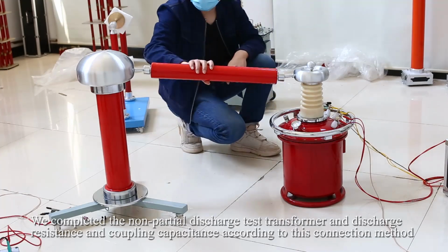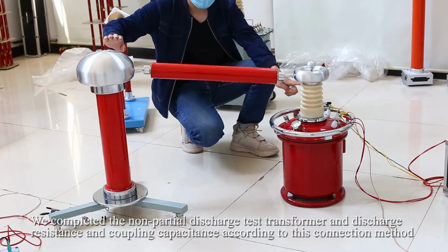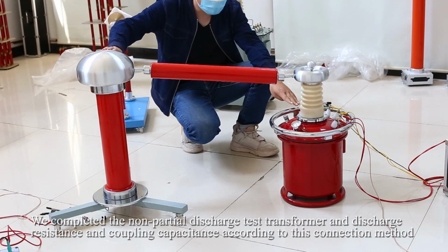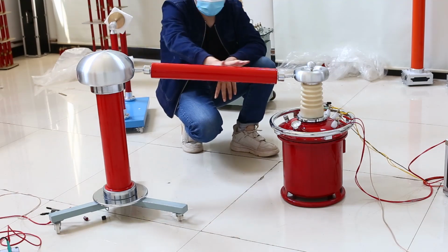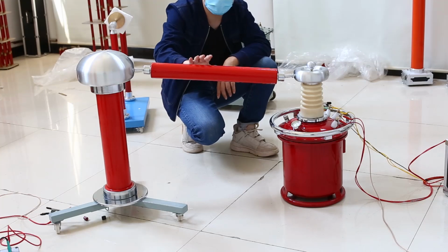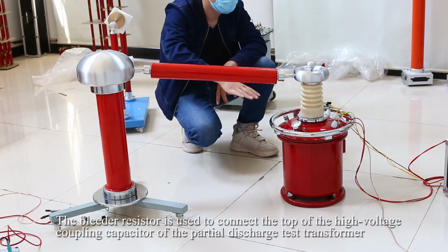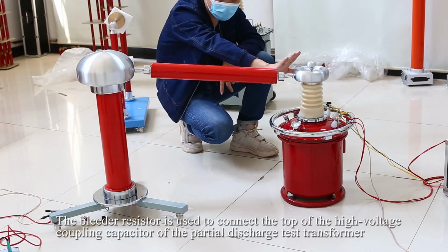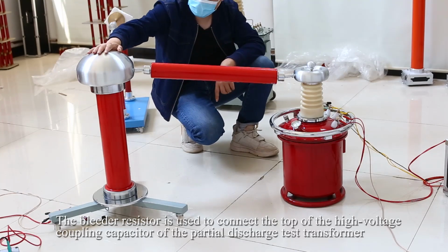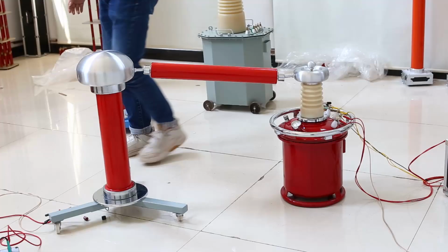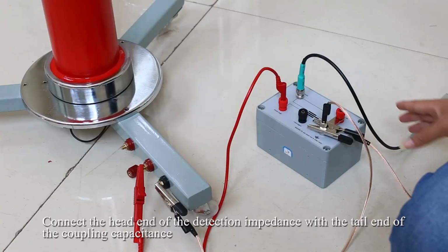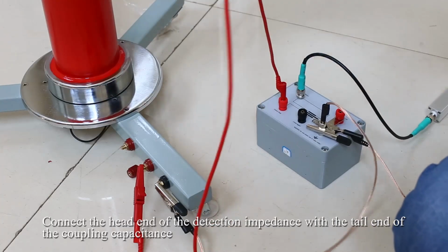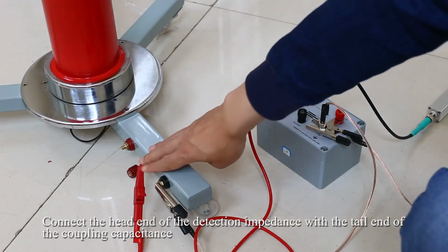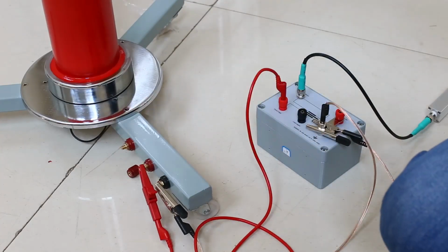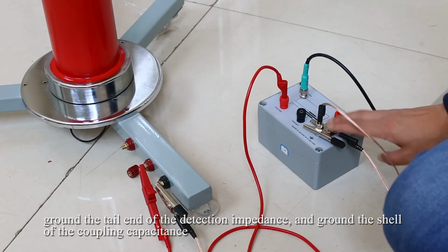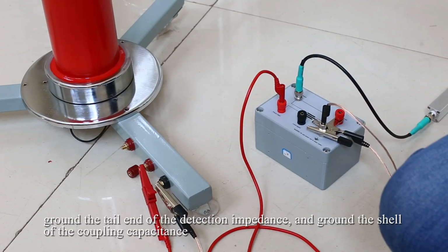We completed the line partial discharge test transformer and discharge resistance and the coupling capacitance according to the connection method. One is the bleeder resistor. The bleeder resistor is used to connect the top of the high voltage coupling capacitor of the partial discharge test transformer. Connect the head end of the detection impedance with the tail end of the coupling capacitance. Ground the tail end of the detection impedance and ground the shell of the coupling capacitance.